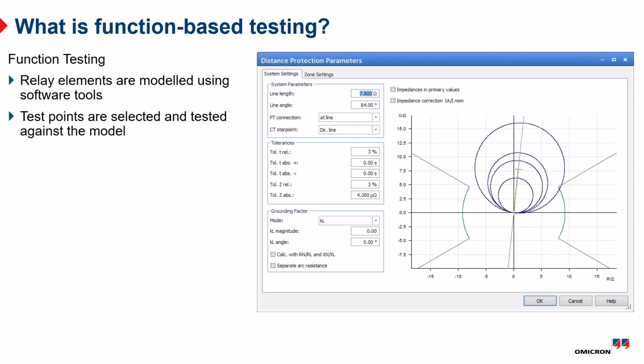So here's an example from what we call our test object, which is a way we create a model of the system. This is our test object for a distance element. Here we put in the line impedances, and you go to the zone settings and put in the relay protective element zones. Once you get done with that, you execute your test, pick your test points, and the software will automatically grade the relay's response.